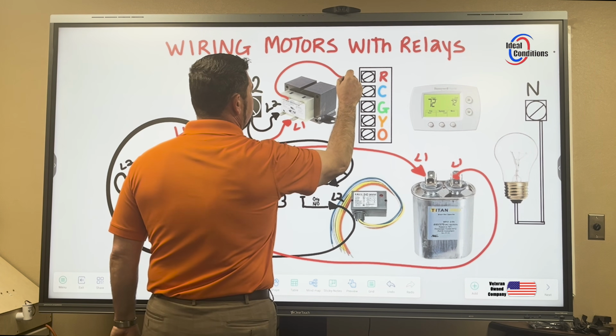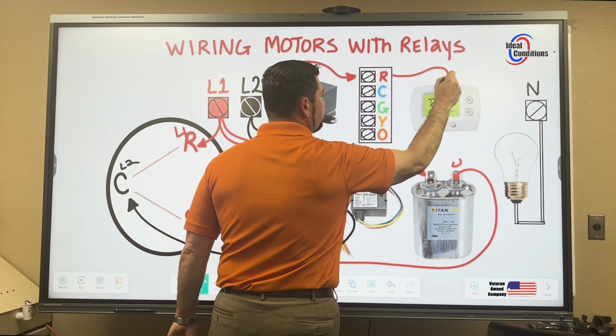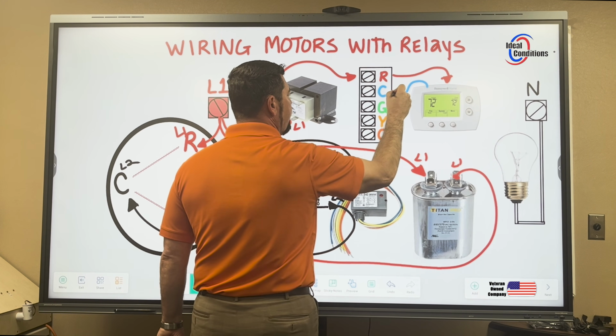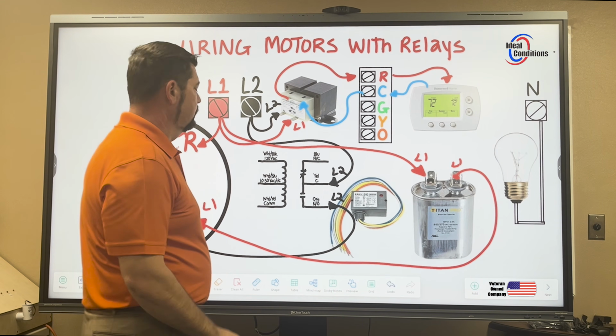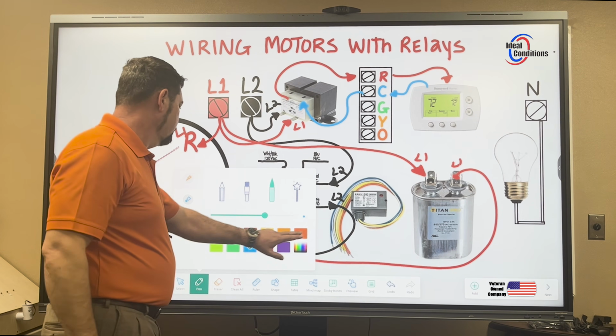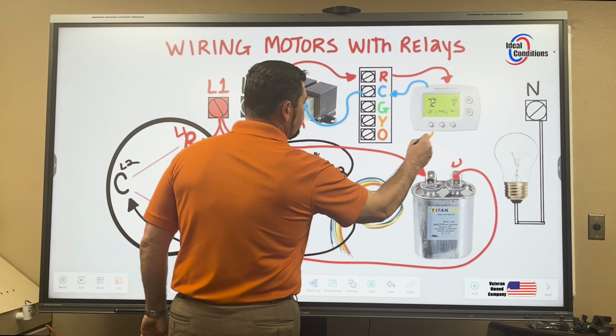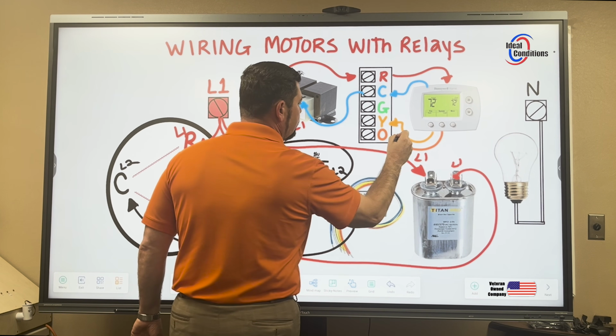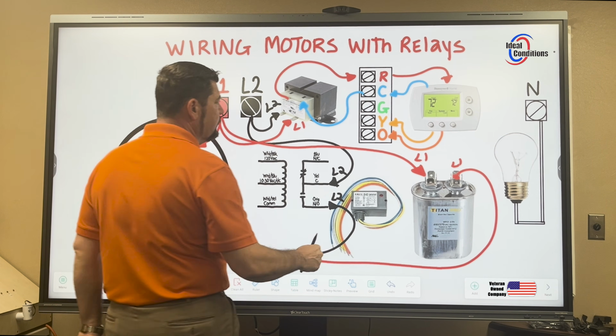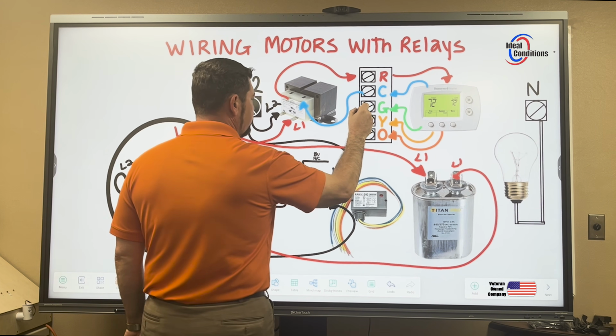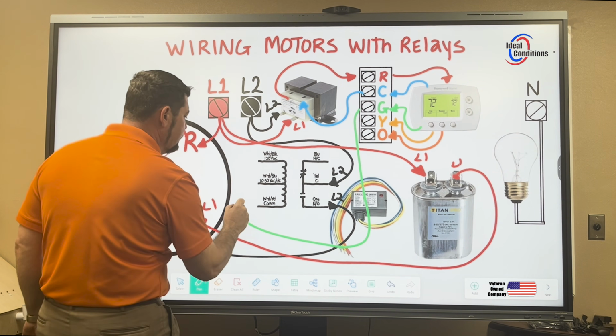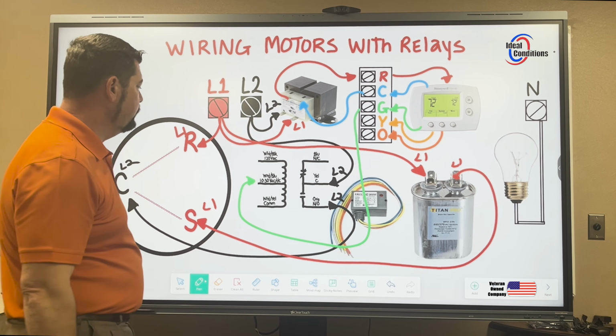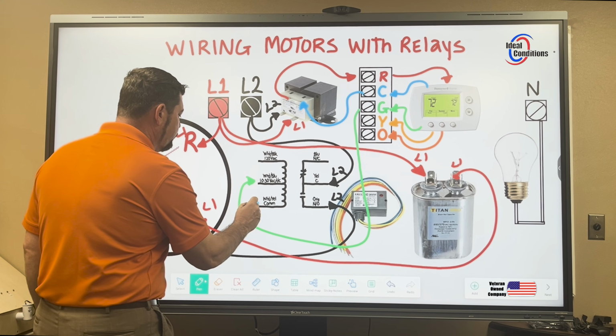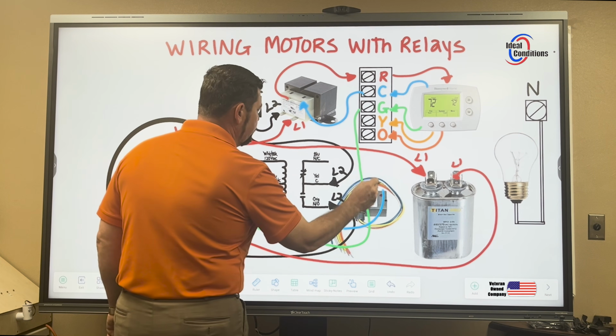We're going to come over here. We're going to wire our low voltage terminal block. We're going to come over to the thermostat, provide it with 24 volts. We're going to give it a path back to the transformer. And as long as we have that, then we'll have everything else. And then we'll have our Y, our O, and the one we're going to wire up to our coil is the G. That's the only one we need to be considering. So here's the G call. We want G to always run in the event that we need the fan to come on, whether it's for cool, heat, or just blower by itself. And then obviously common will be an output. We're going to come back through and wire that back to the transformer.